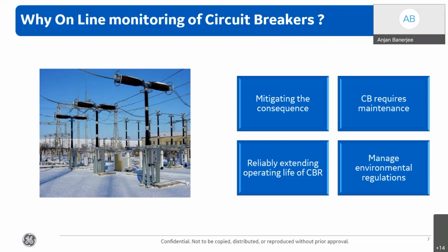Last but not the least, we have heard the circuit breaker uses SF6 as the insulation and arc quenching medium. SF6 is one of the most powerful greenhouse gases known to humanity. So we need an online monitoring tool which would be able to track the SF6 leakage in the atmosphere and would be able to minimize SF6 leakage in the atmosphere.